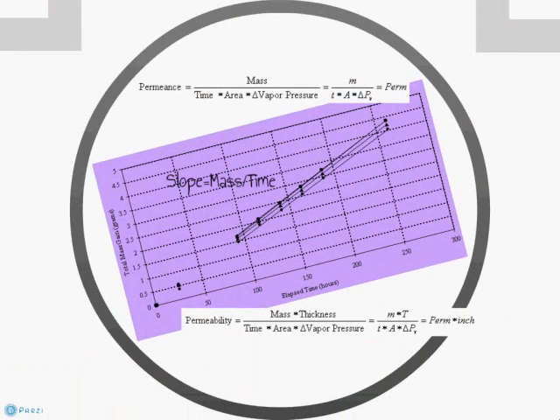Average permeability can be calculated as permeance times thickness, but is only meaningful for homogeneous, non-laminated materials not less than half an inch thick.